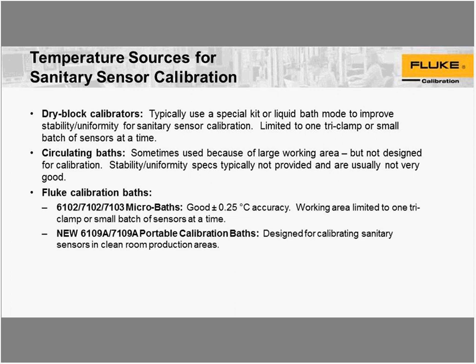Another category is using a circulating bath that's small and portable. Some of these are not designed for calibration, so they may not have the specifications needed for a calibration process, like stability and uniformity, for example, which may not be specified. If they are designed for calibration, they may be fairly large, with known uncertainties.